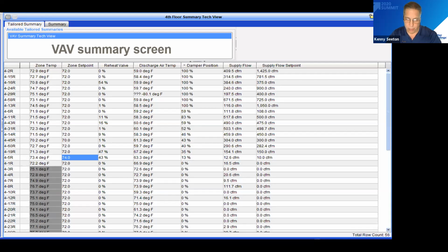If you look in the middle where it says damper position, the first 16 are above zero, meaning all the zeros you can't see are because the damper position is at zero since nobody is in the space. This is critical now with COVID, because that building is maybe only 30% occupied. By doing this, we're able to shut down the air conditioning or supply air to all those spaces.